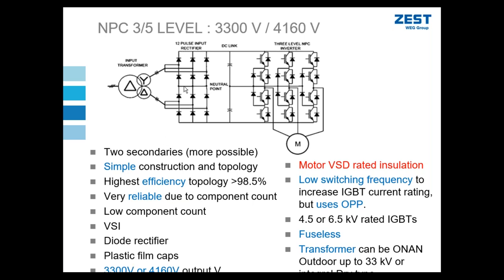We are limited in this topology to 3.3, in fact to 4.16 kV as the maximum output of this topology, and that's because we have reached the limitation of the voltage capability of IGBTs at that voltage output. 11 kV and higher IGBTs are under research, but to this point are impractical for use in VSD applications. This topology, you'll see why later, but the motor does need to have a VSD rated insulation.